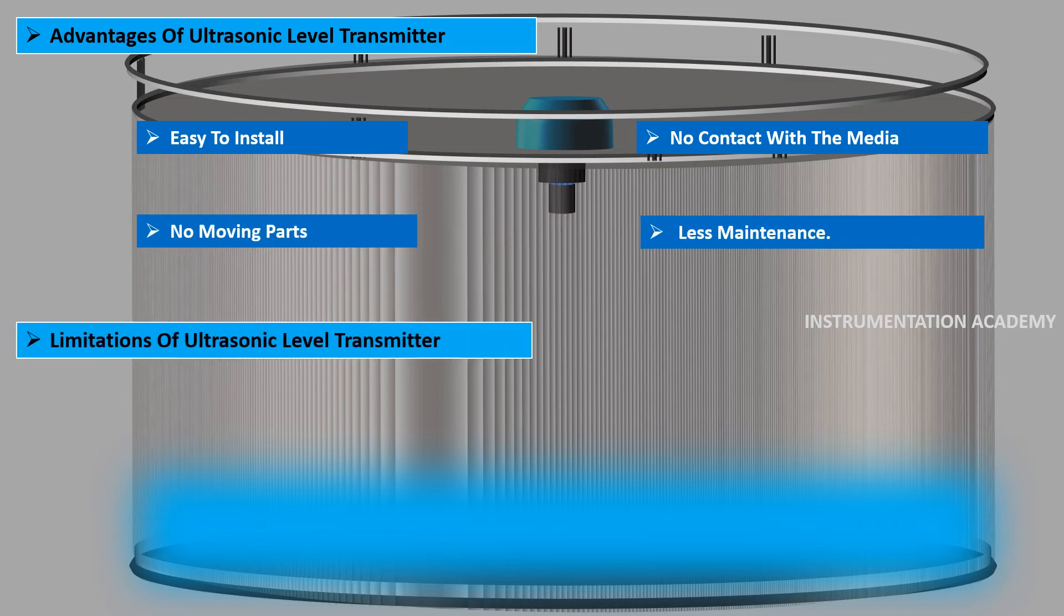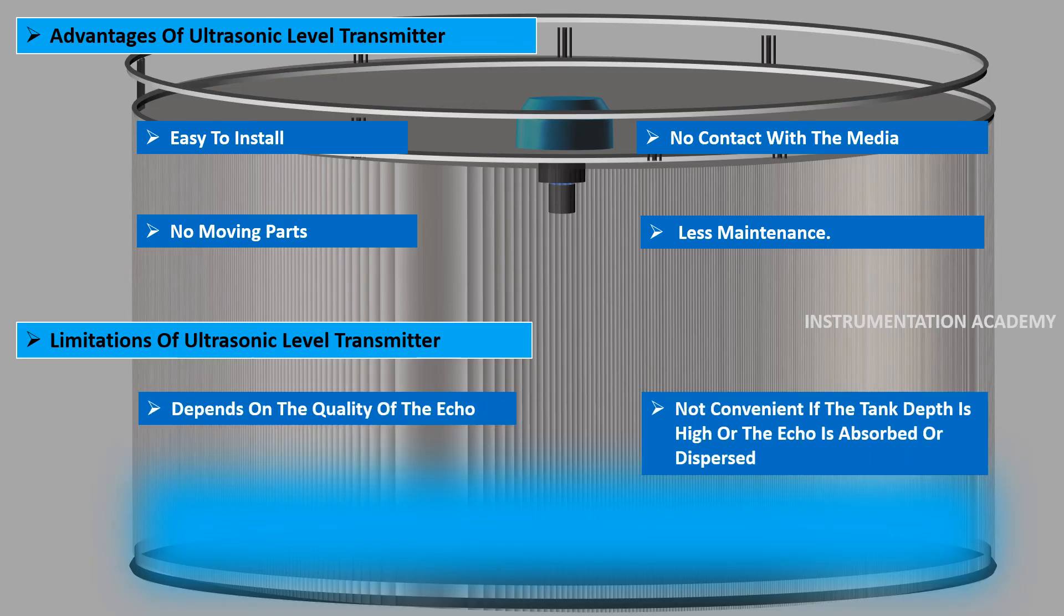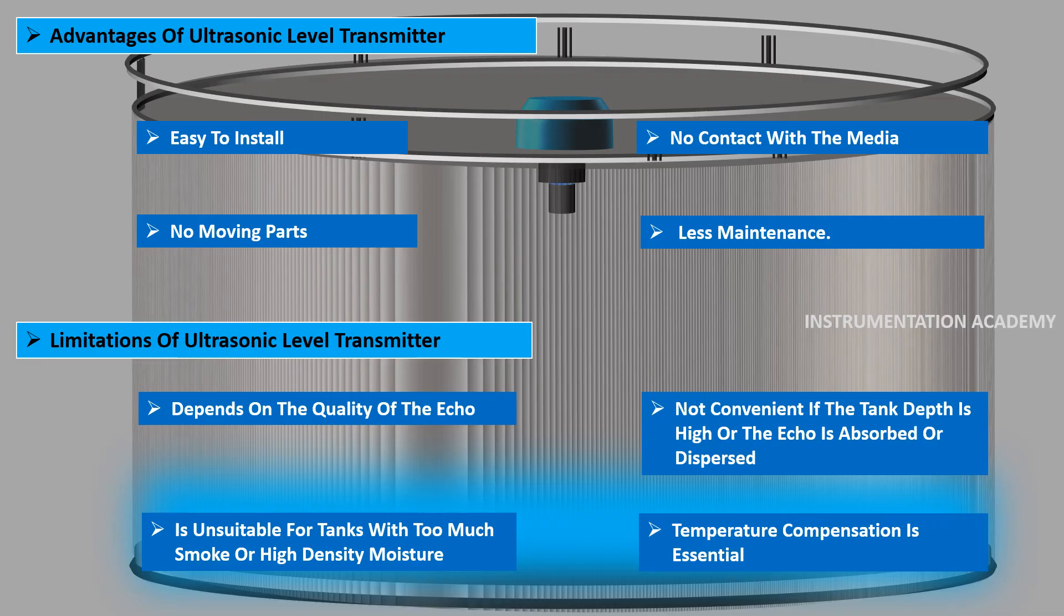Limitations of ultrasonic level transmitter: Accuracy depends on the quality of the echo received by the transducer. It is not so convenient if the tank depth is high or the echo is absorbed or dispersed. It is unsuitable for tanks with too much smoke or high density moisture. Changes in process temperature will change the speed of ultrasonic wave through the space above the liquid, so temperature compensation is essential.